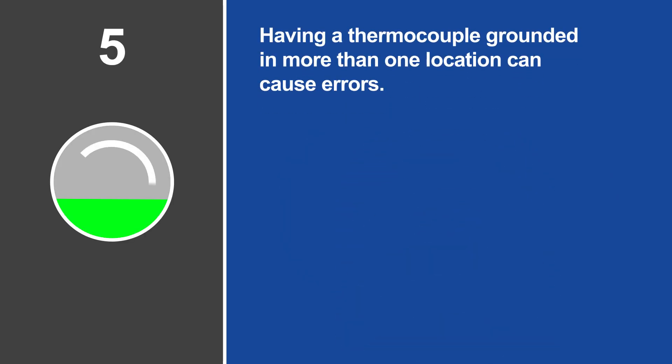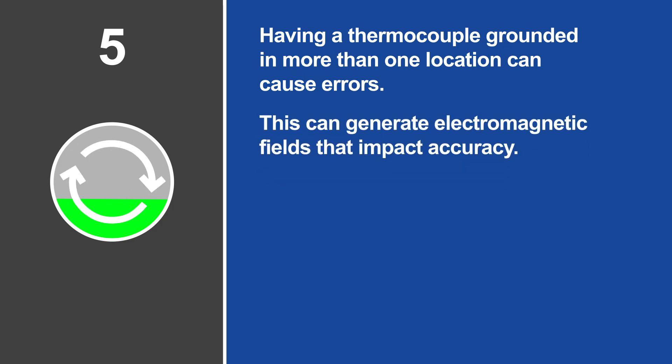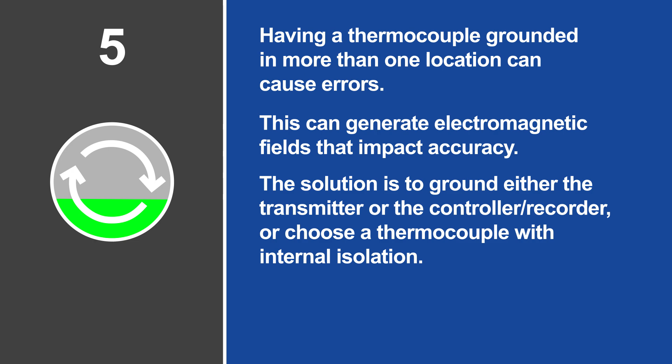Having a thermocouple grounded in more than one location can cause errors. When this happens, a ground loop can occur, causing electricity to flow around the loop. This can generate electromagnetic fields that impact accuracy. The solution is to ground either the transmitter or the controller recorder, or choose a thermocouple with internal isolation. Loop isolators can also prevent this from happening.